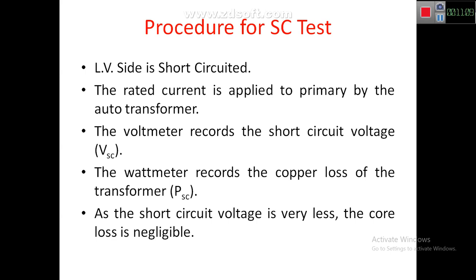In the procedure, the LV side is short circuited and the auto transformer is adjusted until the ammeter shows the rated current. The voltmeter records the short circuit voltage VSC, and the wattmeter records the copper loss of the transformer, PSC. Since the short circuit voltage is very small, the core loss is negligible.